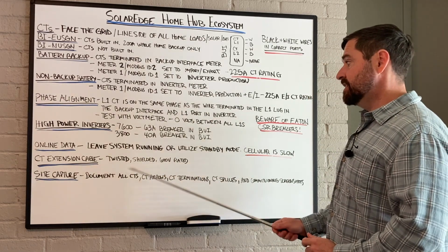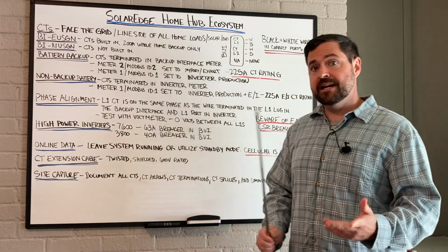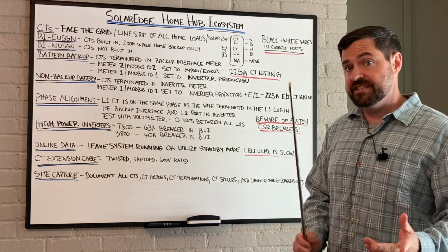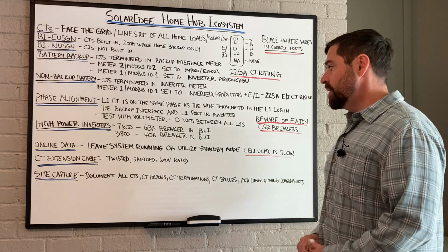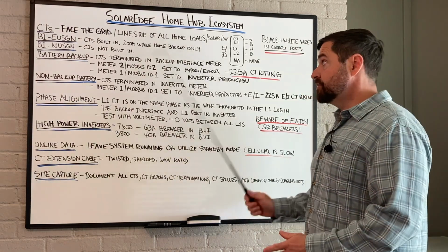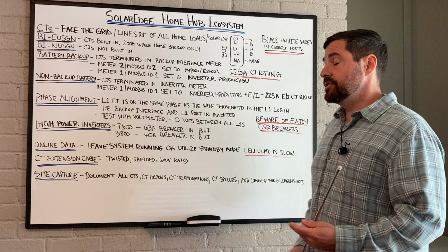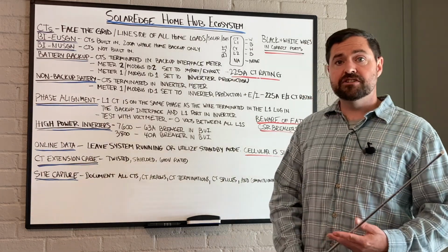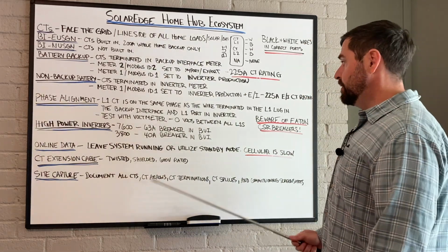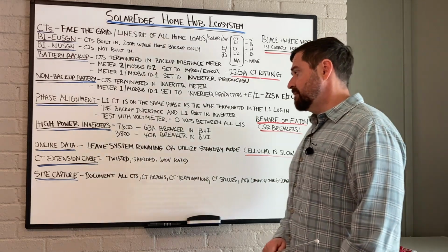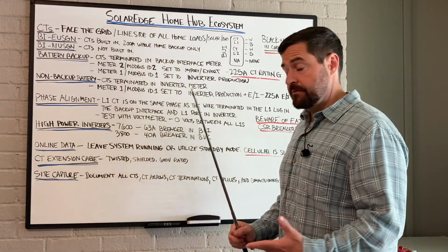So the twisted and shielded is to prevent electromagnetic interference, which will scramble the CT readings. 600 volt rated is more of a code issue. With SolarEdge, you're talking high voltage DC. If you have communications wires in that same compartment, they're required by code to be the same voltage as the system.